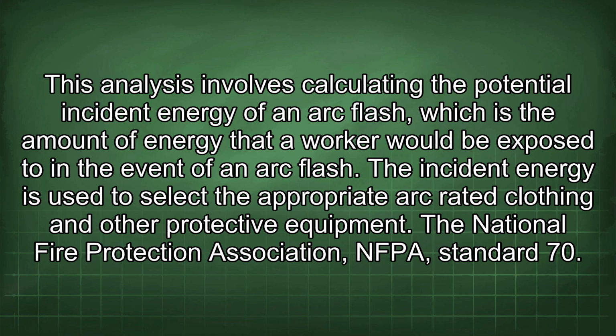This analysis involves calculating the potential incident energy of an arc flash, which is the amount of energy that a worker would be exposed to in the event of an arc flash. The incident energy is used to select the appropriate arc-rated clothing and other protective equipment.